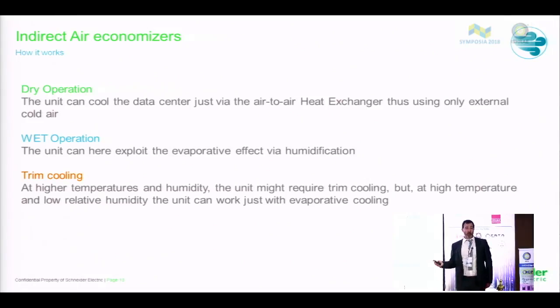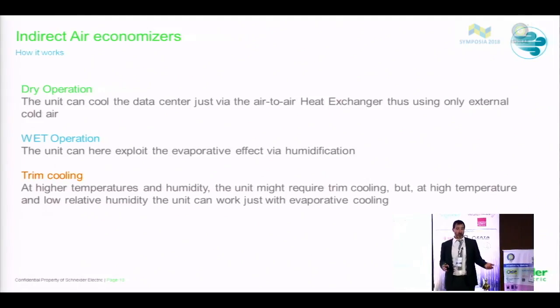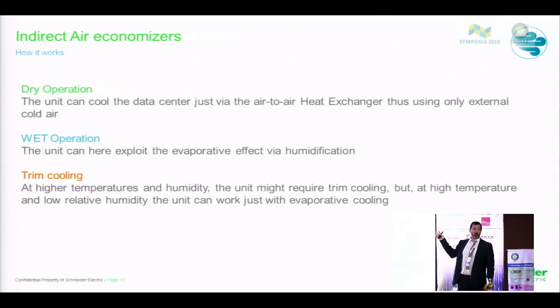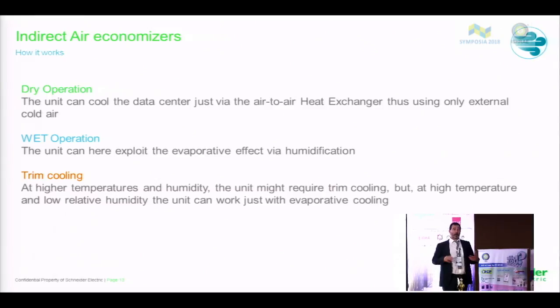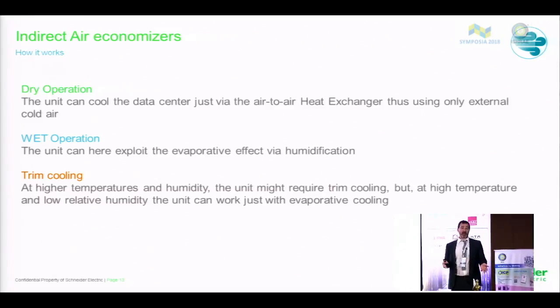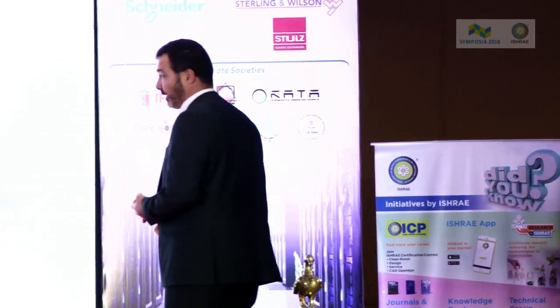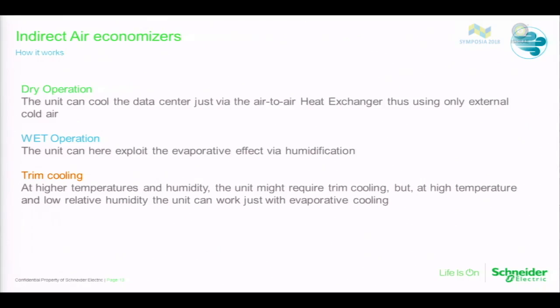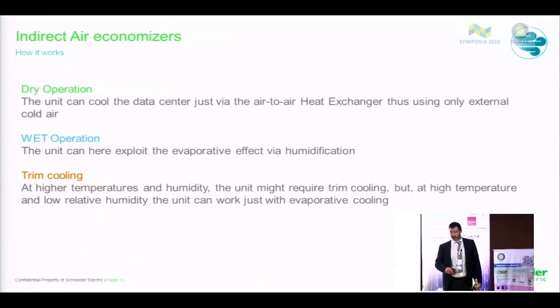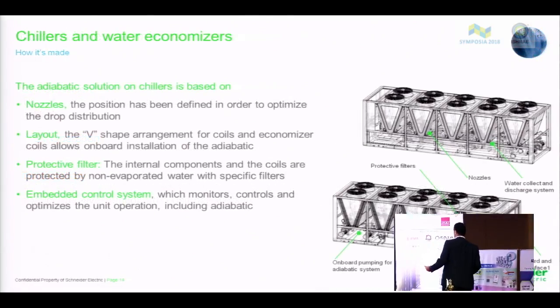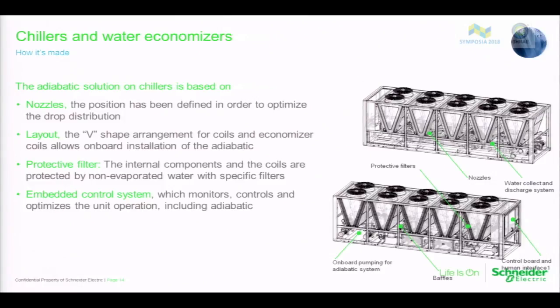And that's the reason why we have both solutions, because we cannot try to convince you that the air economizer is the best solution or the chiller is the best solution. Both of them are good solutions that depend on the water cost, the water availability, and the ambient climatic profile. For sure, if the water is available and cheap, and if the humidity is not extremely high, this is the best solution to reduce the total cost of ownership. No discussion about that.